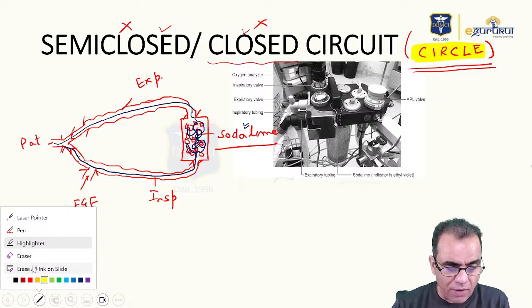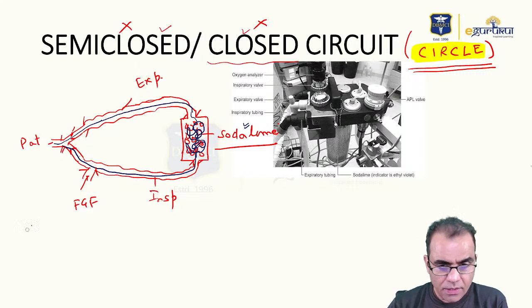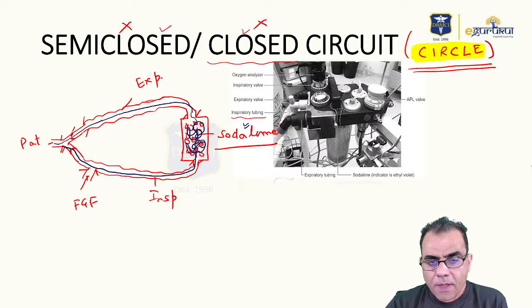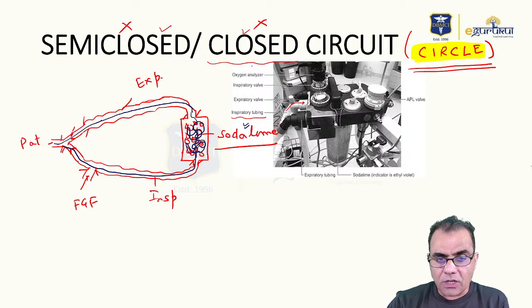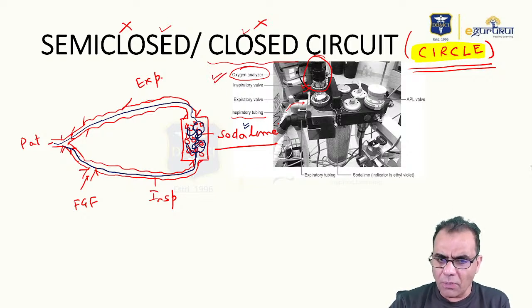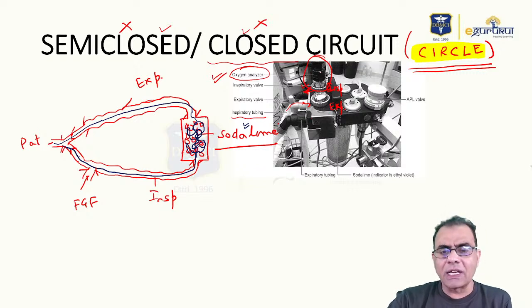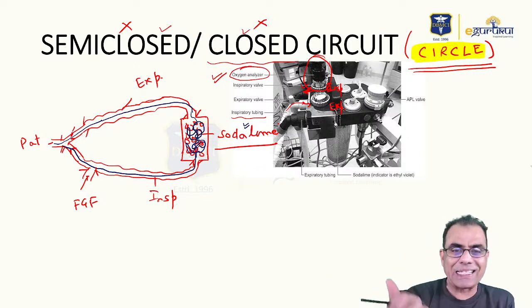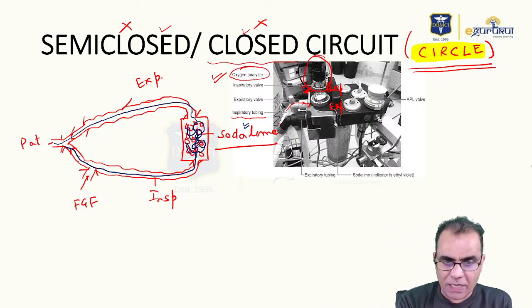So you can see the diagram here. This is the inspiratory limb, the inspiratory tubing. How do we say it is the inspiratory limb? Because there is an oxygen analyzer. The limb where the oxygen analyzer is fitted is the inspiratory limb. Although it will also be marked, either with an arrow like that, or in some machines written as I or E, or INSP or EXP, the oxygen analyzer will always be on the inspiratory limb because it tells you the final delivered concentration of oxygen to the patient.